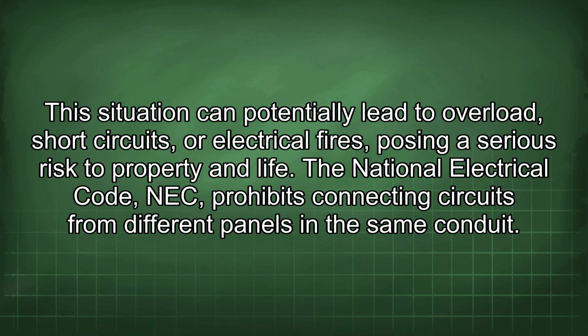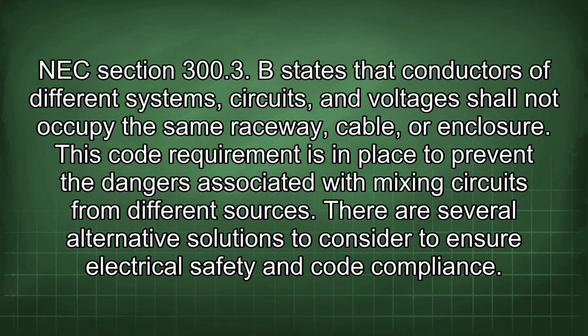The National Electrical Code, NEC, prohibits connecting circuits from different panels in the same conduit. NEC Section 300.3 B states that conductors of different systems, circuits, and voltages shall not occupy the same raceway, cable, or enclosure. This code requirement is in place to prevent the dangers associated with mixing circuits from different sources. There are several alternative solutions to consider to ensure electrical safety and code compliance.